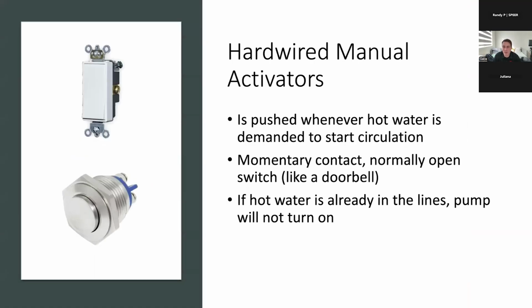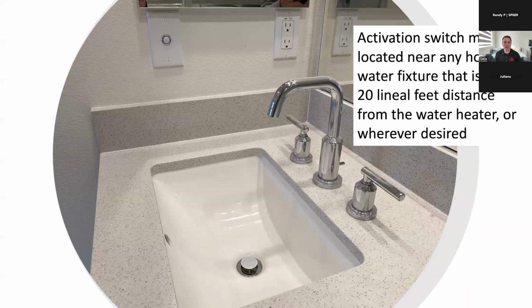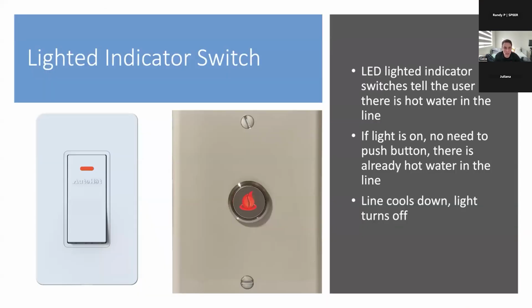So what types of methods for activation? We have hardwired activation. These are momentary contact, normally open switches. So think of a doorbell. A lot of builders are putting a little push button activator near the light switch or near the fixture itself, and that commands the pump to turn on. There are lighted switches that illuminate when hot water is ready. So if there's hot water in the line, this indicator will tell the homeowner, okay, hot water is ready, all I've got to do is turn on the faucet. And then when the lines cool down, the light will turn off, and that prompts the user that they need to prime their loop to get hot water.